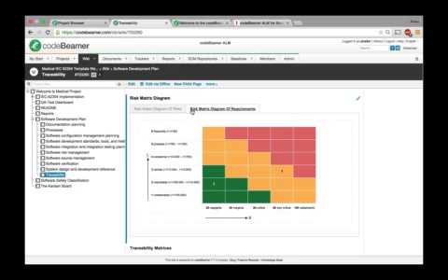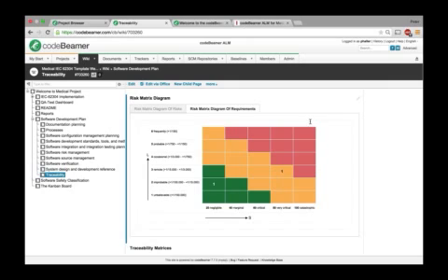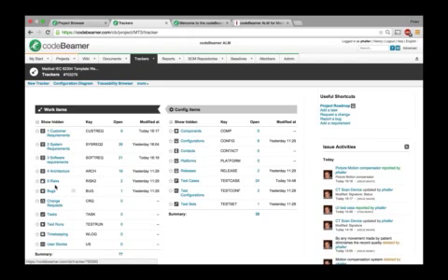Once we click to the risk matrix diagram of requirements, and click on the same item again, you see the requirement is now in the first column, which is the timer mechanism, and the same risk, the time frame set by operator is not respected by the software. So you can have an overview in this two-way direction. Now let's go back and generate our risk.